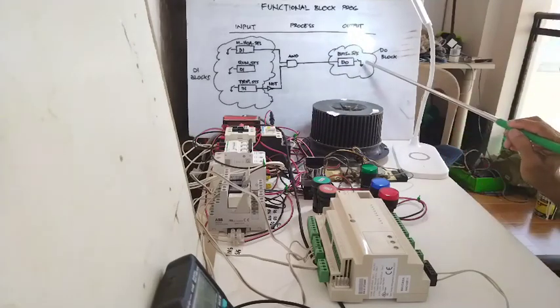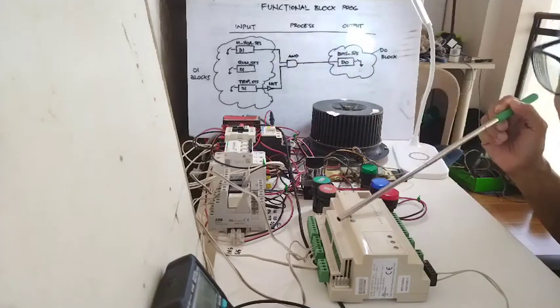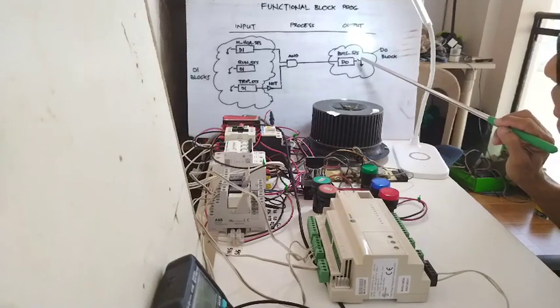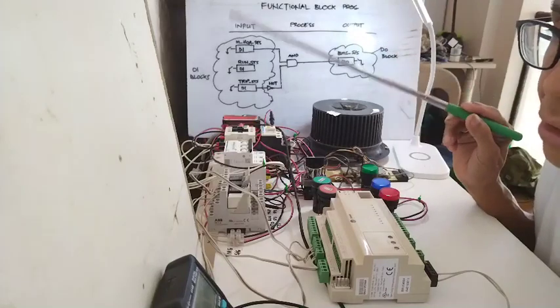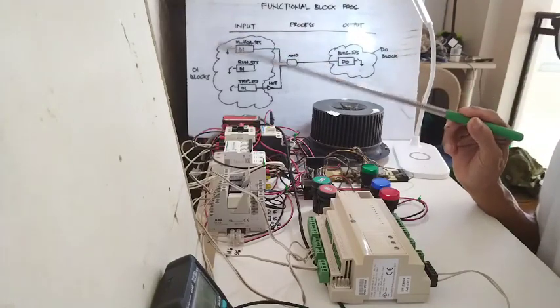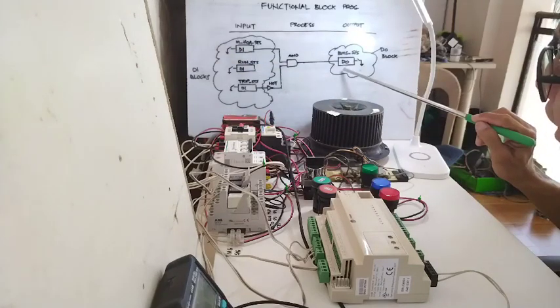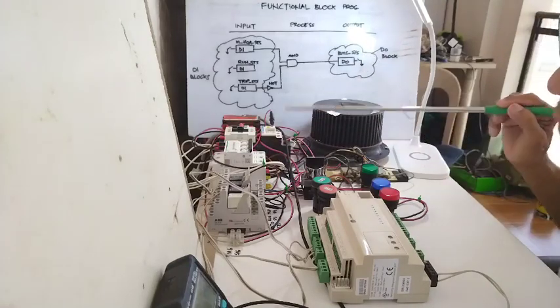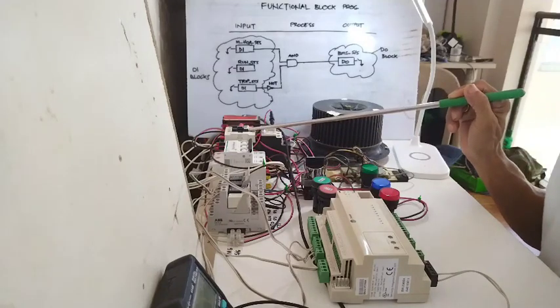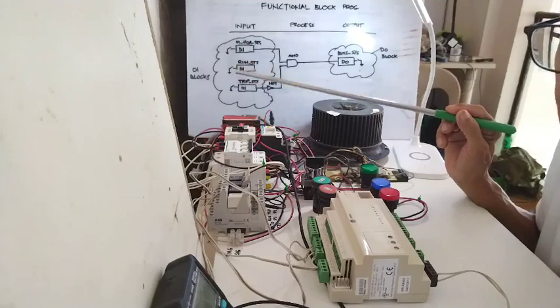That output goes to the DO block. The DO block has a built-in relay in my controller. This relay will activate a contact, and this contact is the one that goes to our control panel — the BMS start/stop. When the output is 1, this contact will close. Then 24 volts will go back to the control panel and start the magnetic contactor, as shown in my auto-position control wiring diagram.